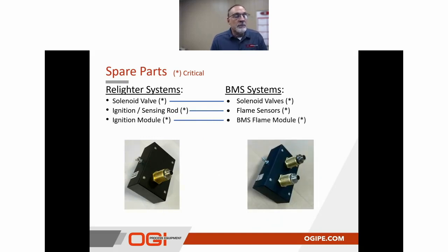Ignition module for the relighter system or a BMS flame module: no matter what system you have, for relighters or BMS systems, these flame modules are extremely important. Not having one on hand, and obviously if you have multiple systems out there, one or two of those on the shelf really will pay dividends. Either way, those flame modules are what sense the flame and actually control the BMS or relighter systems. So essentially, it's the brain of the operation. Everything else is literally relays and solenoids. So having those as part of your spare parts inventory is extremely important.